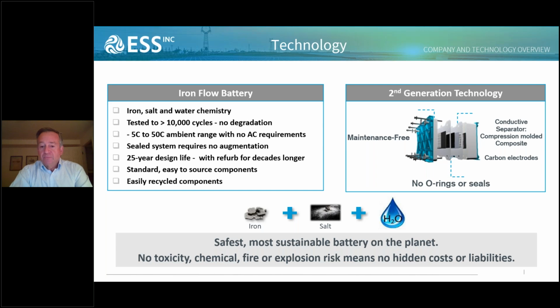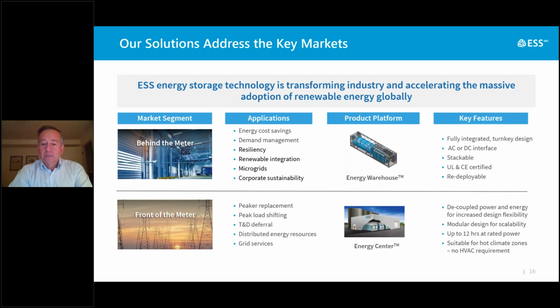We have two platforms we're going to market with. For the behind-the-meter market, we have a containerized solution you can see in the middle. The electrolyte is kept in a tank, which takes up about half of this 40-foot ISO shipping container. The battery modules are stacked on the other end, along with the battery management system, the DC-DC electronics, and for an AC version, string inverters.